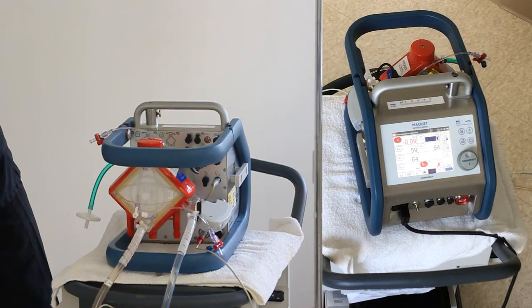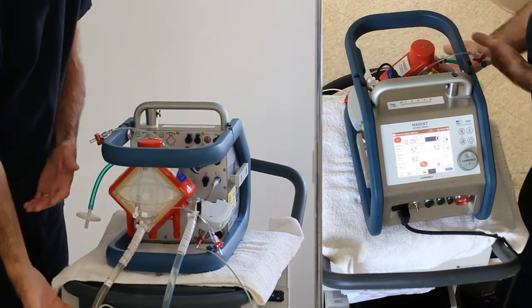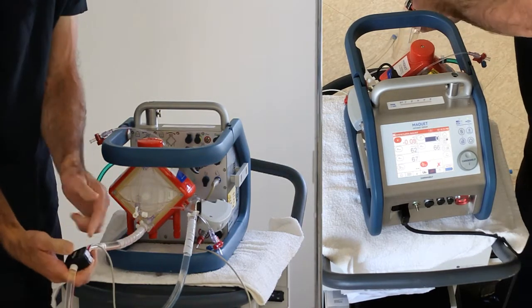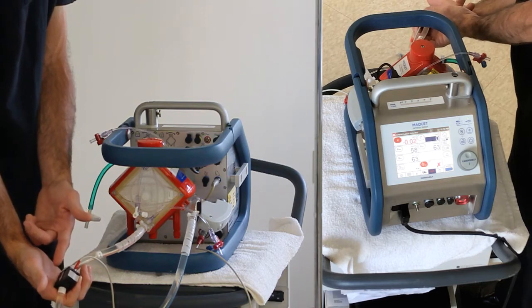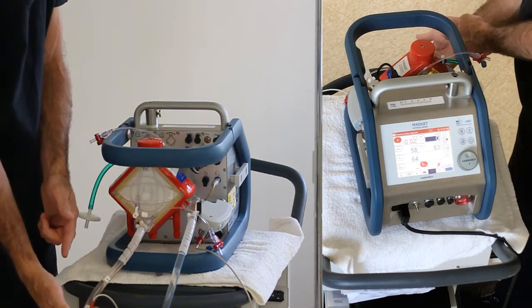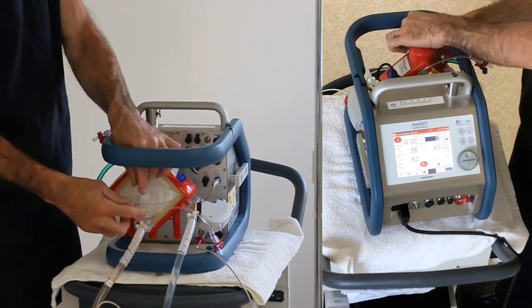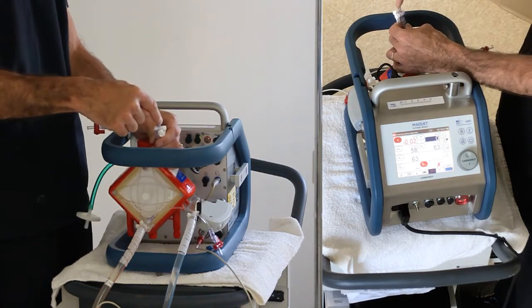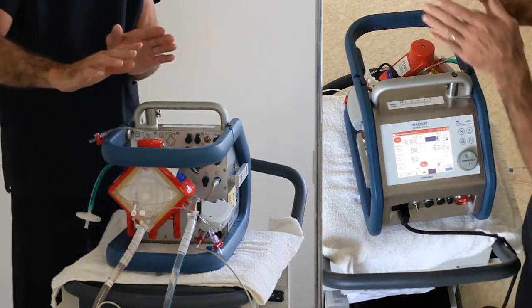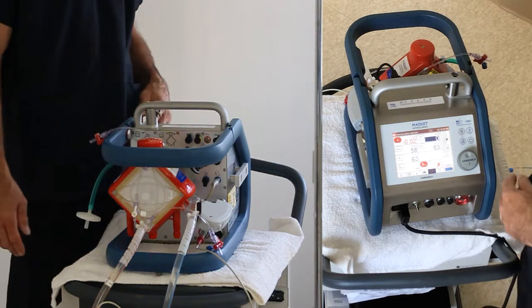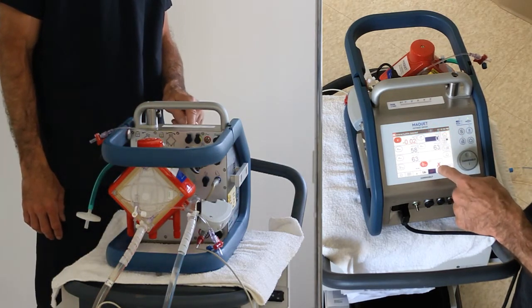Now I should check that out. I should look for air along the arterial side. I should maybe find the open bubble detector, if indeed that's what it is. That's a super simple fix. If there was real air, I've got to walk it into the oxygenator, and I'm going to pull it out through this port up here. And then when I've confirmed that the patient is safe from air, we can come over here to our screen.